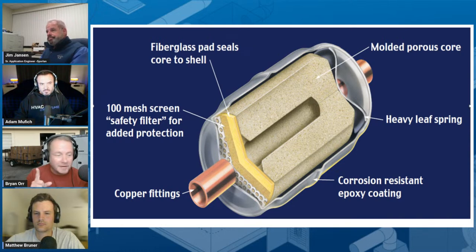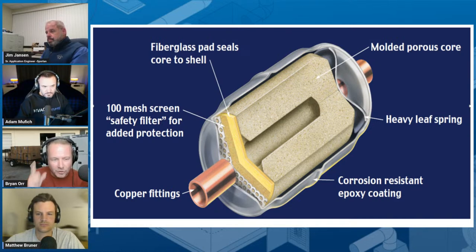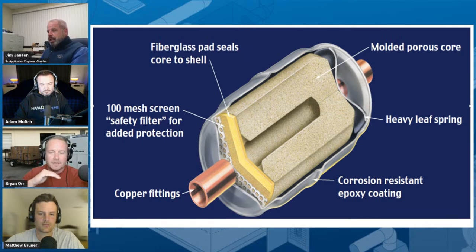To be clear — that is specifically a filter only, no desiccant. We see this a lot in racks when you have removable and replaceable cores. Sometimes you literally just leave essentially a strainer in there — just a very simple filter to catch, but no desiccant. So there's no moisture removal or acid removal. All it's going to do is get the hammer handles and the lunch boxes.